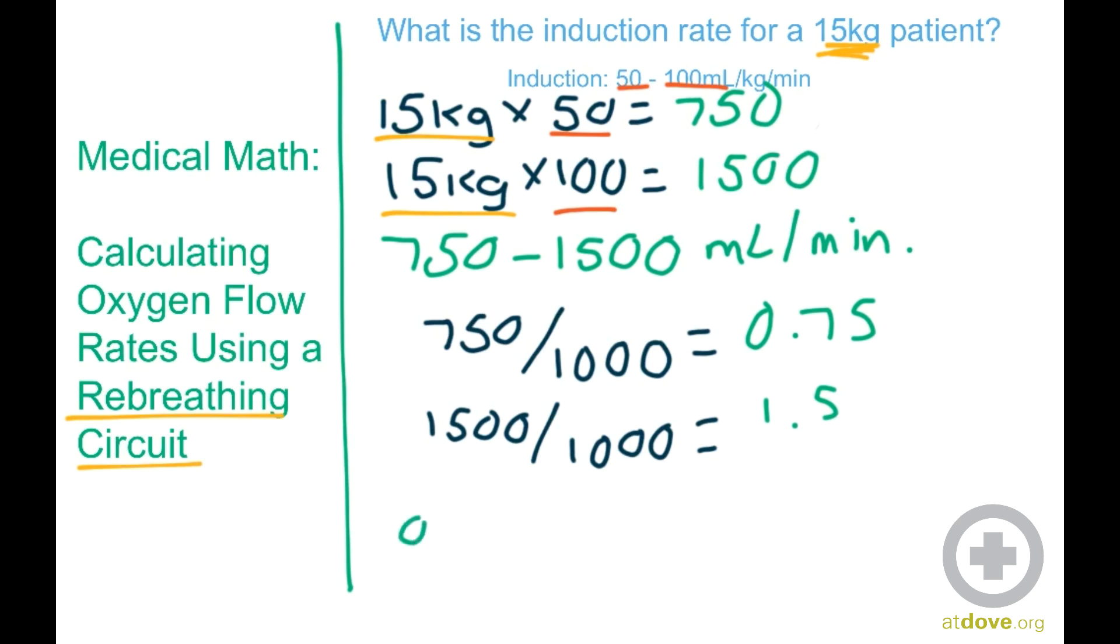So our end result here is 0.75 to 1.5 liters per minute, which is the value we need to actually put into the oxygen flow meter. The 750 was the low end of our induction range, and 1,500 was the high end of our induction range, and that's just to convert it from milliliters into liters. So your end result is 0.75 to 1.5 liters per minute.